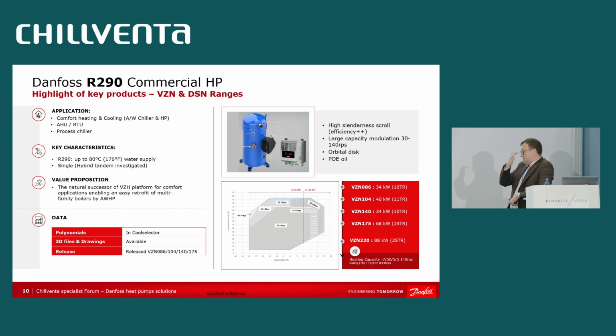The compressor has been designed primarily for heating application, so we are able with these compressors to go from minus 15 evaporating up to 82 degrees condensing. That means roughly minus 5 ambient, and we are still able to produce water at 80 degrees. We go up to 25 degrees SST. Everything is already available, and supply temperature can go up to 80.